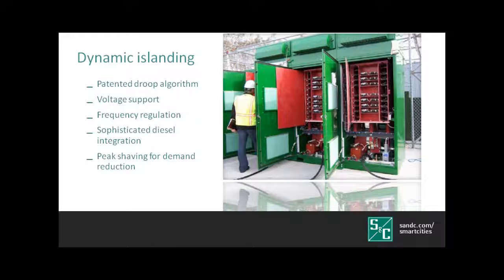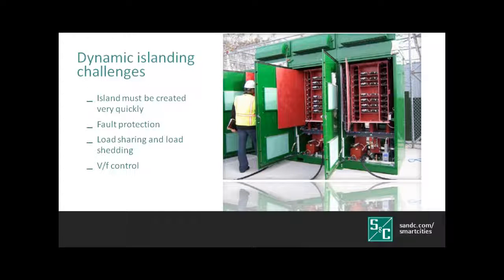It also can provide frequency regulation and sophisticated diesel integration. This means that in islanded situations, true remote communities and islands running their microgrids fully off diesel, you're able to mitigate that use of diesel and use alternate forms of generation first. It can also do peak shaving for demand reduction in large commercial and industrial customers, using alternate generation to reduce demand charges as well as shift peak energy to off-peak.